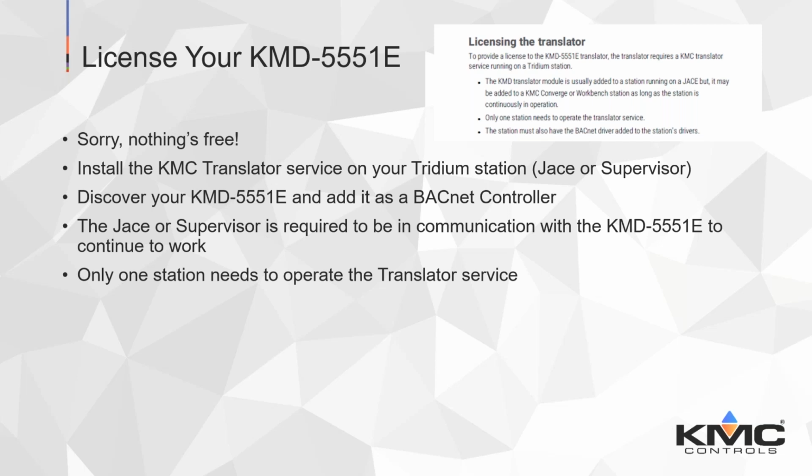When you hit the BACnet Discover button, it's going to discover the translator and all of the controllers right off the bat. At that point, you're just working with Niagara normally. You pull in all the controllers, then go into the points folder and pull in all the points for each individual one.